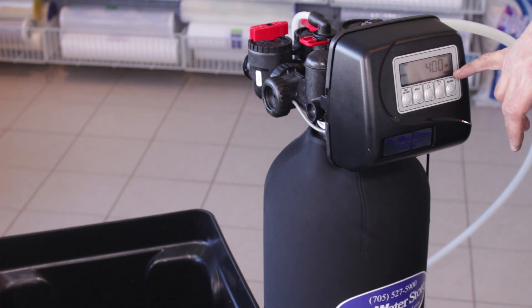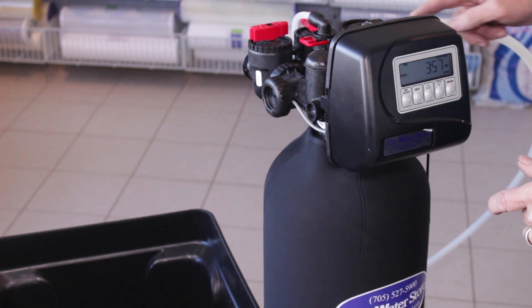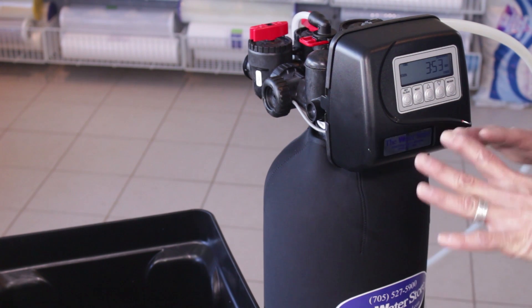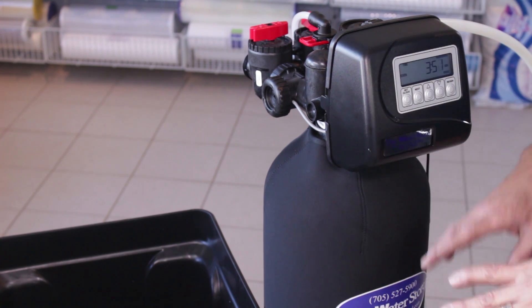So now we can see that it's showing rinse here and it's started counting down. Now water will be flowing to the drain again and what that's going to do is rinse the media but it's also going to settle the media back down and that's what we want it to do.